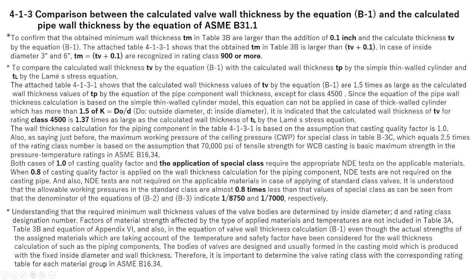Now we summarize the valve wall thickness and the pressure temperature rating class. The valve minimum wall thickness TM obtained from Table 3A, Table 3B, and the equation of Appendix 6 shall be used for inspection purposes. All these obtained minimum wall thicknesses TM are greater than the thickness tv determined by equation B-1, as TM is larger than TV plus 0.1 inch.